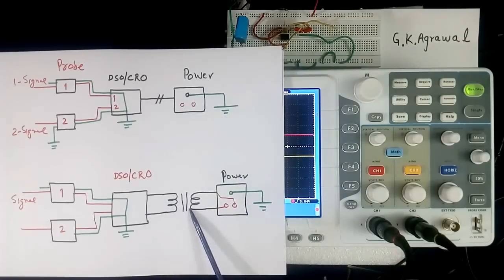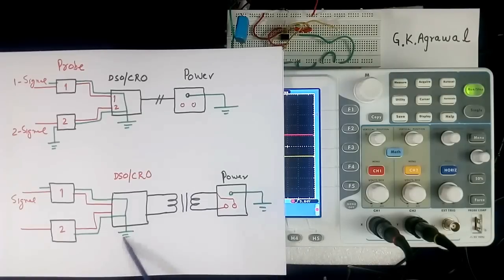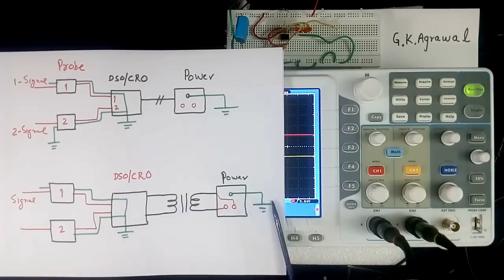Now this is another way of using CRO. In this we connect an isolating transformer between incoming and CRO. This is 1 to 1 transformer. In this case, this grounding of AC input signal and this power supply can be different. I have shown same. It can be common, it can be different.